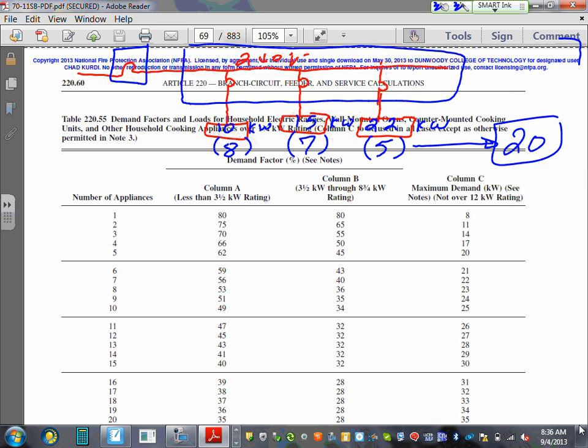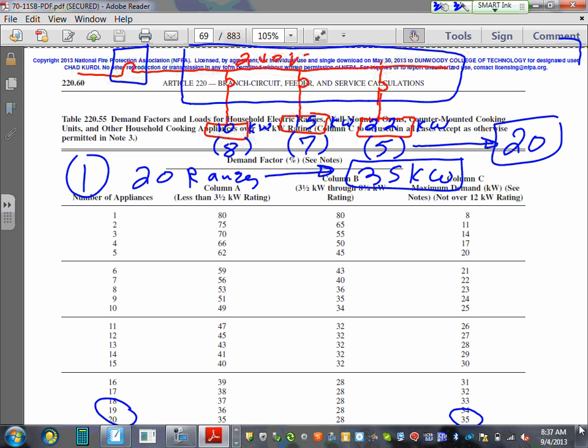Okay, they're all under C, but there's one little problem: some of them are over 12. So step number 1, for 20 ranges, what's the demand from the table? 35 kW. Had all these ranges been 12 or less, we're done. But are they 12 or less? They're not. Some of them are more than 12, some are not. So that's step number 1. Step number 2.